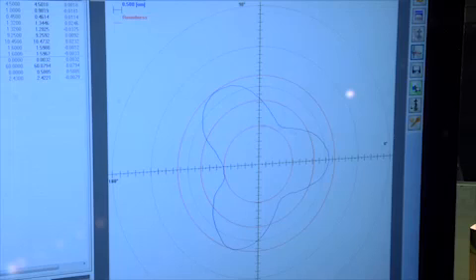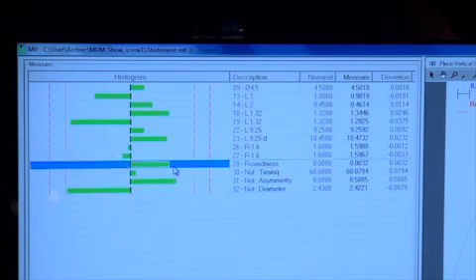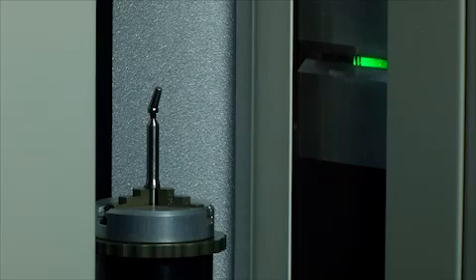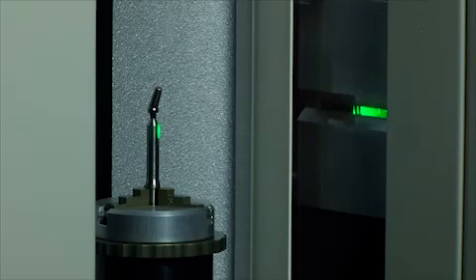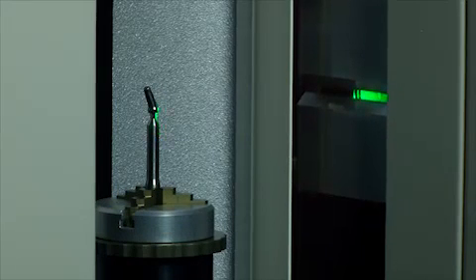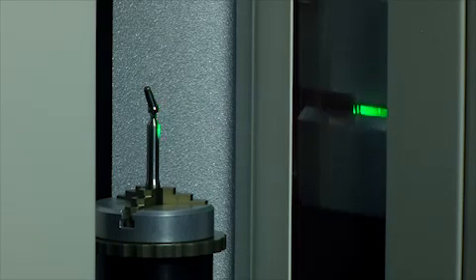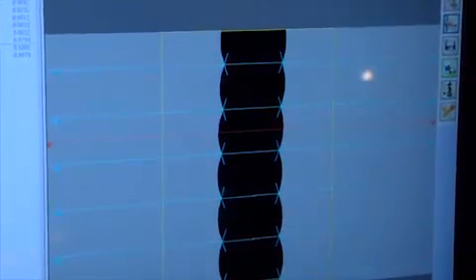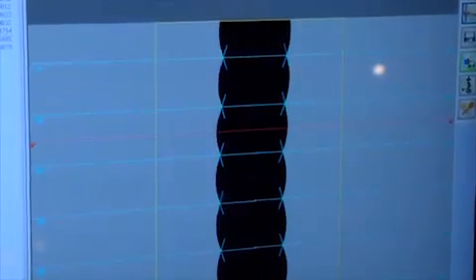As part of the rotation measurement, you can get roundness plots. And within each of these dimensions, you can look at a measure trend to see what's happening with your process if you're measuring multiple parts. Also, as part of the rotation, you're able to get angles between clocked portions of the part. For example, this part has a nut on it, so you can get the angles between the nut faces as well as asymmetry and diameter of the nut.